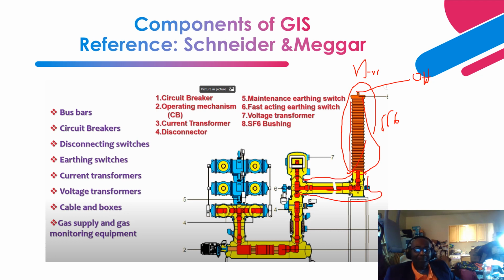And remember, I made mention that it is compartmentalized, right? Okay, so this compartment, as you can see over here, is separate from this compartment, right, through a barrier. So there are barriers that prevent, basically when there's a problem here, it doesn't come here. When there's a problem here, it doesn't come here, and vice versa. Okay, so this one is the VT, the voltage transformer, and disconnect switches, earthing switches, right? Then the current transformer, the circuit breaker, the operating circuit for the circuit breaker, right? Disconnect switches.